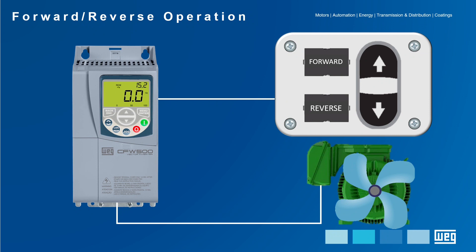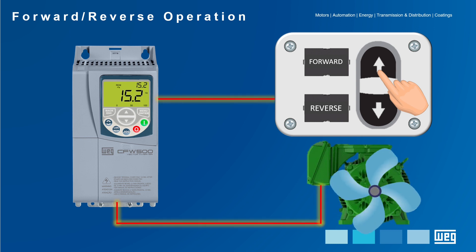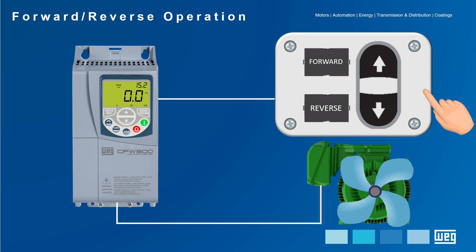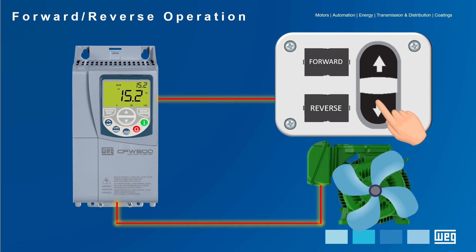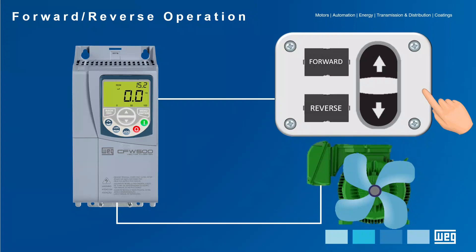After finishing the digital input connections and adjusting the parameters, it can be seen in the operational representation that by keeping the UP arrow button pressed, the drive starts the motor clockwise, respecting the acceleration ramp up to the reference speed, and when the same button is released, the drive decelerates the motor by ramp until it stops. The same happens when the DOWN arrow button is pressed — the drive switches the direction of rotation and starts the motor counterclockwise. When this button is released, the motor stops. These were some of the commands used in the CFW500 inverter drive.